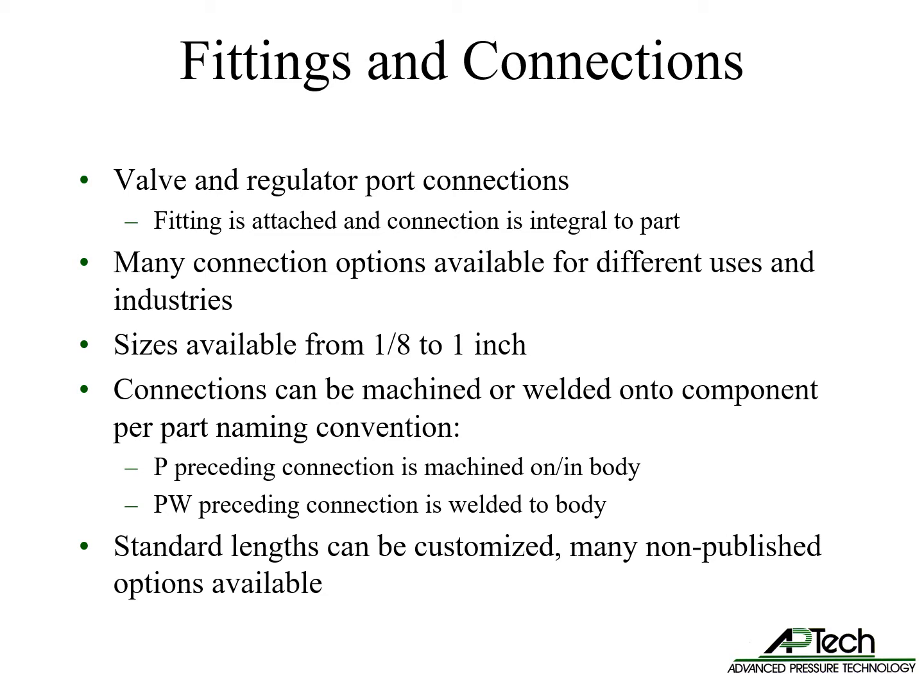APTech's available sizes are from 1/8 inch to 1 inch. Connections are either machined or welded into or onto the component. P preceding the connection means machined connection, and PW means welded connection. Standard lengths can be customized to meet competitor dimensions or specific system requirements.